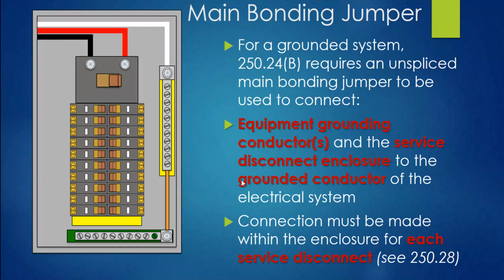Now, this is an example of the one I was talking to you about earlier, where instead of the green screw being up here in this grounded terminal lug, they've added an additional bus, maybe they needed more terminations here. So down here, they put an equipment grounding terminal bus and mounted it to the enclosure. And up here, typically, this is floating in this case because there's no main bonding jumper in it. But what they've done is install the screw here, and they've connected these two buses together to act as one, and they used a wire type main bonding jumper. Now, of course, if they do that, you're going to have to size this main bonding jumper. It is not factory installed.